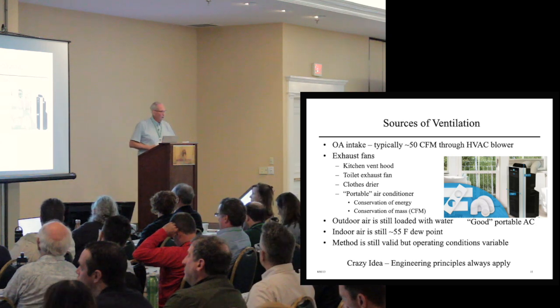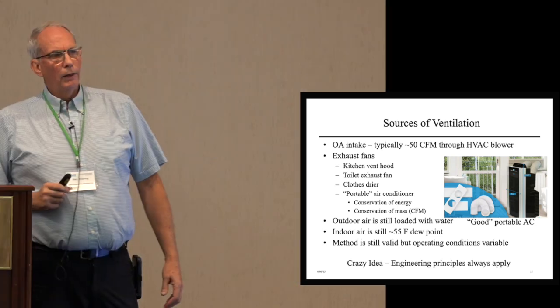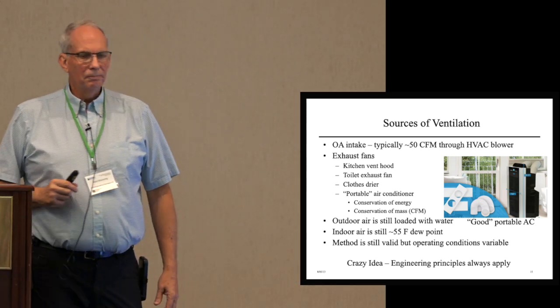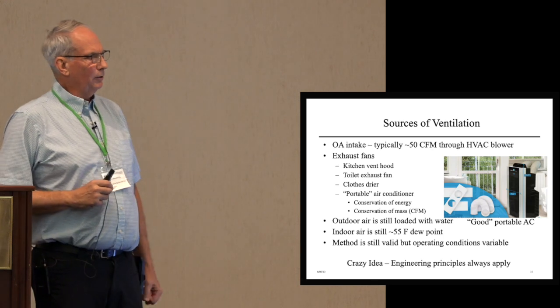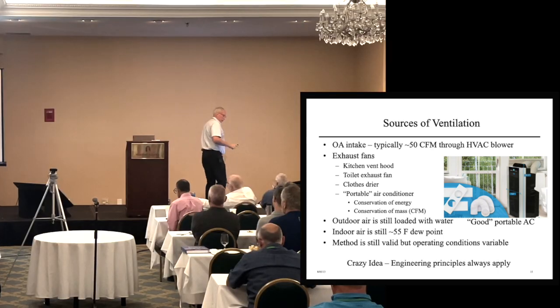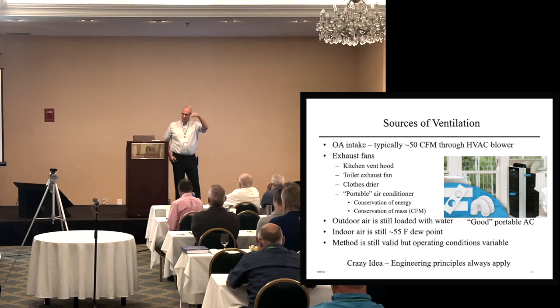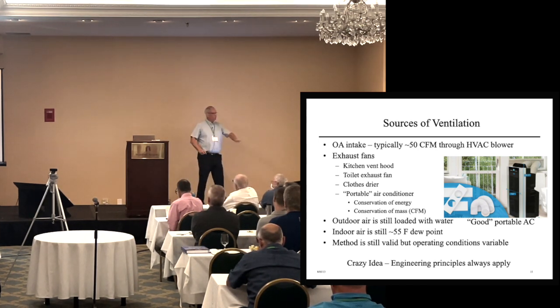But here's one that really got me. Went to a house, middle of a lawsuit, the upstairs air conditioner quit working. What did they do? You don't hire a contractor to make it work again. You go to Home Depot and you buy a couple of portable air conditioners that have one hose that goes out the window. I know this is a tough concept, but if there's one and only one hose going out the window, it's an exhaust fan.